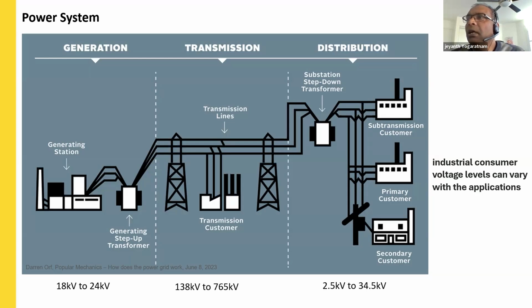When it comes to the consumer or end user end, again, the distribution substation comes into the role. Those substations have the step-down transformers, which will step down the voltage to different levels. It can vary from 2 kV to 34.5 kV, or in some instances, we might go up to 66 kV as well. And when it comes to the residential application, we will be seeing along the road pad mount transformers as well as pole mounted transformers, which further step down the voltage to 120 to 240 volts, which are connected to the residential loads.